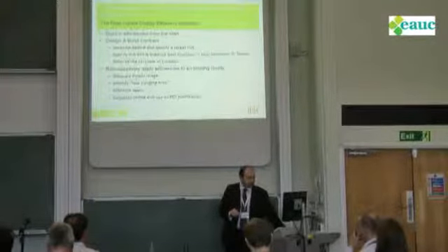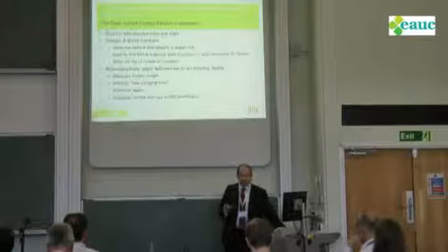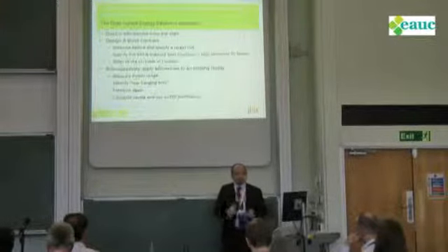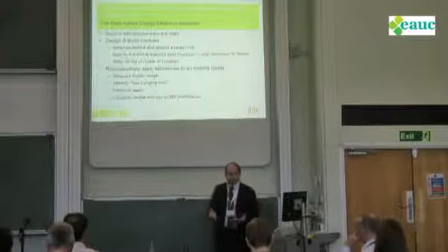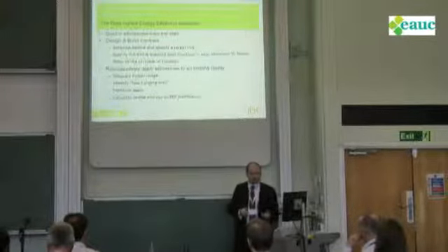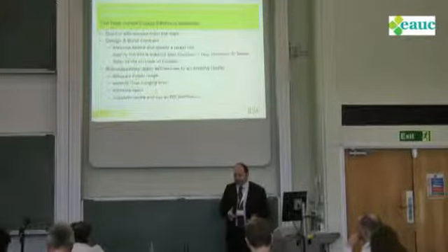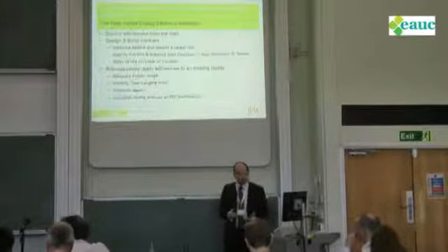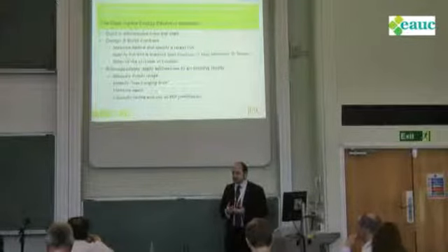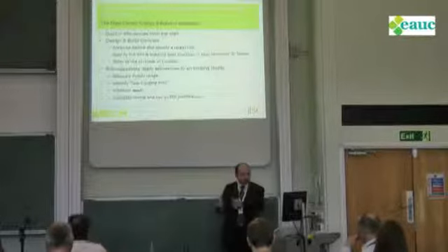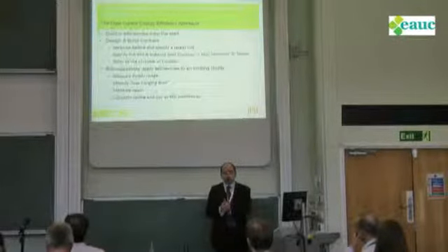And of course, if you want to achieve a certain level of energy efficiency, then you've got to be able to measure what your efficiency is before you even start. So make sure you know what your PUE is. First thing you've got to do is put some sub-metering in, so you can measure the power coming into your facility, and when you've finished, you'll have a target PUE that you want to achieve.